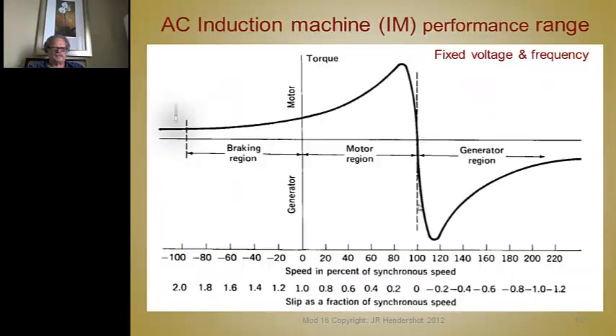I don't have any pictures of those, but this is what I was talking about before, about the torque speed curve with fixed voltage and frequency. And here we see the motoring region and the generating region. And so when you're motoring, the motor is trying to run at synchronous speed, 100% synchronous speed, but whatever load's applied is going to slow it down. So it's going to slow down to this point until it hits the breakdown torque, and then it's going to stall.